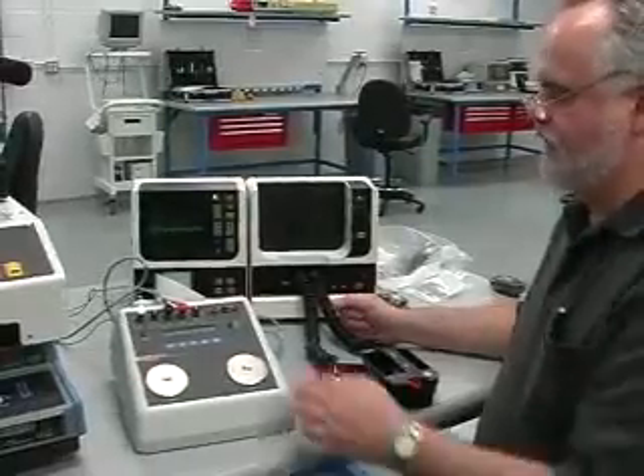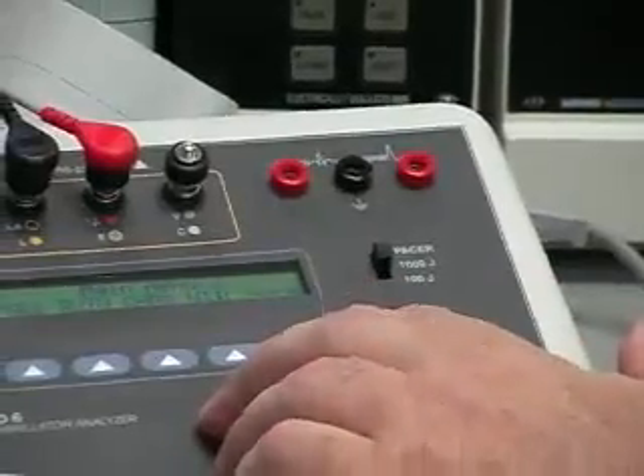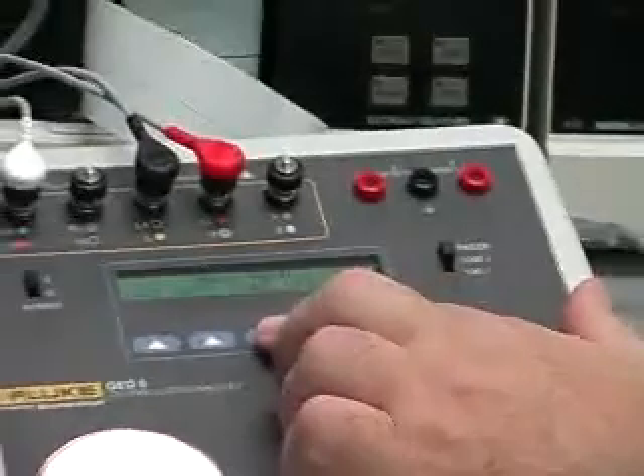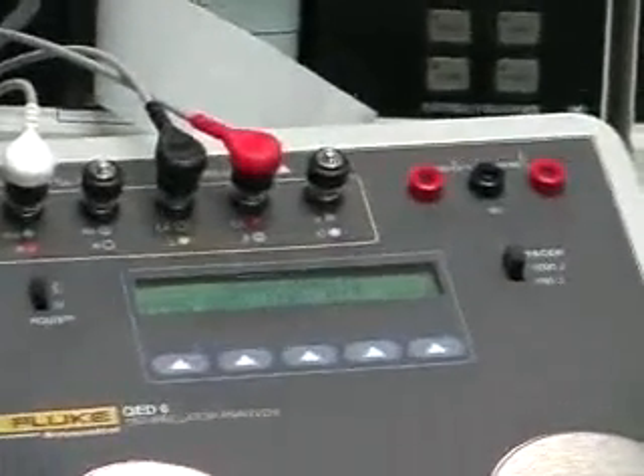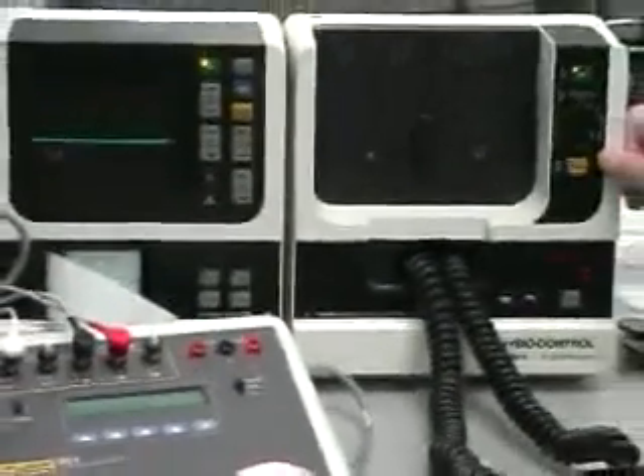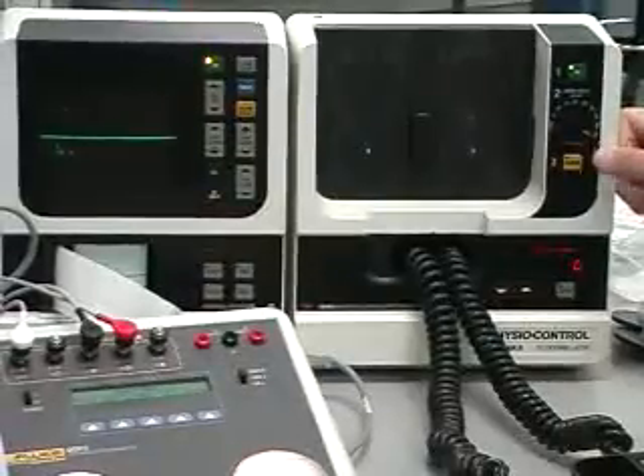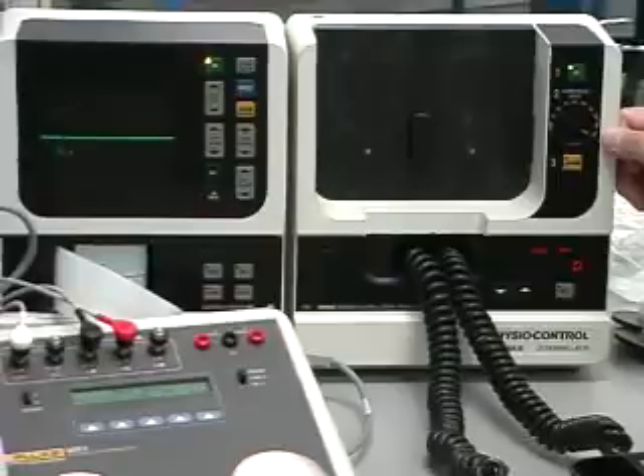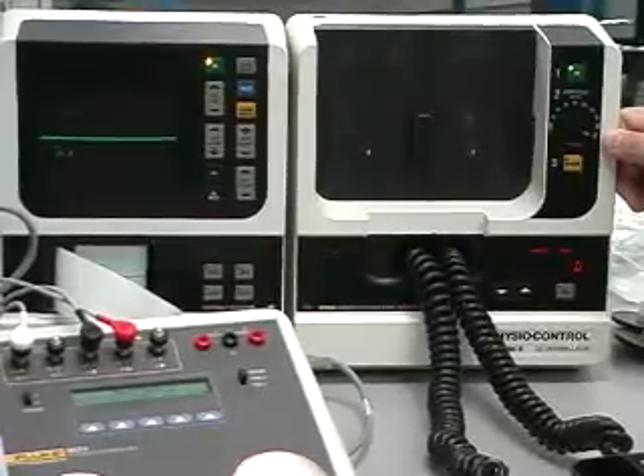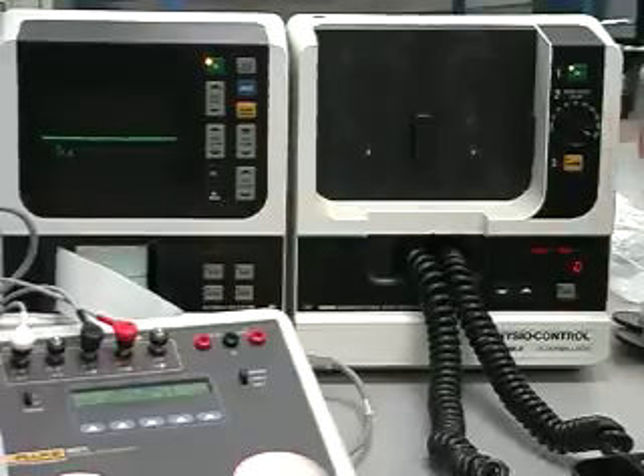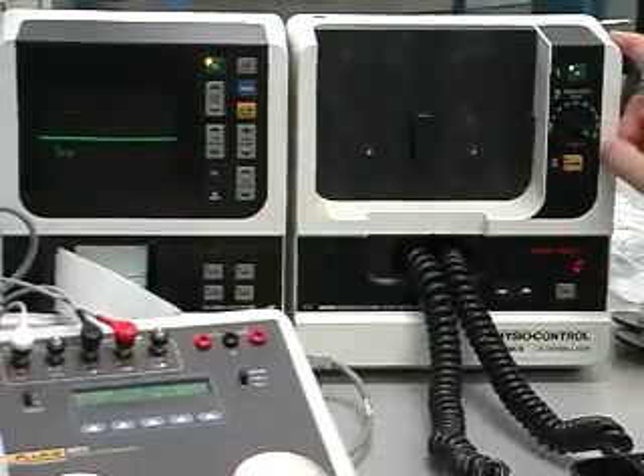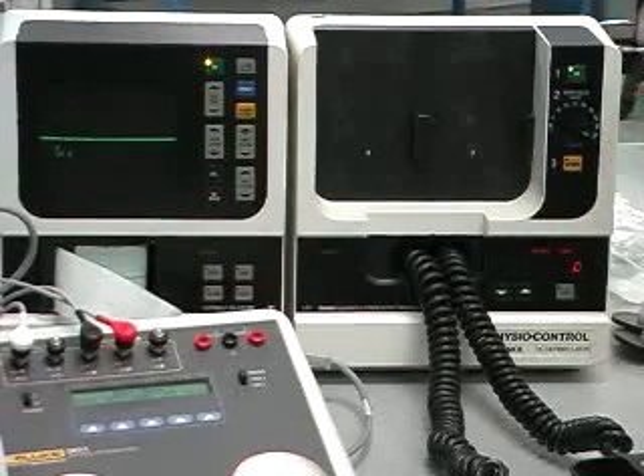Okay, now also the other energy type tests that we were talking about. We have what's called the charge test, and this would be a matter of just going up to the maximum level available in a defibrillator, this being 360 joules. And with this, typically you're looking for values of under 10 seconds for the defib to charge and discharge on that 10th attempt. And typically that would be running on battery operation. We'll just leave it plugged in for this demonstration.